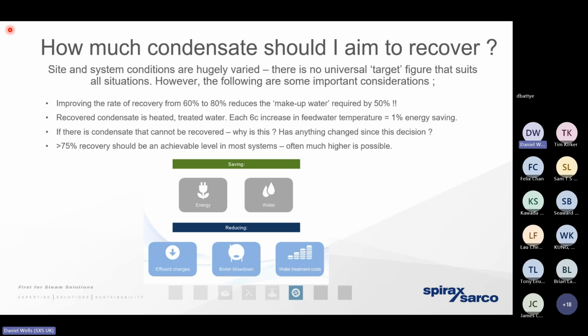It's a little bit more tricky than that, because we know that our client is highly likely to have a number of steam traps that maybe failed in the open position. We know that we may need to vent condensate away if it becomes depressurized and expands significantly. We know that we may have the occasional leaking steam valve or pinhole in pipework, for example. So it's fair to say that in the vast majority of applications and cases, we can work on a rule of thumb that says we should really be looking to recover about 85% of all of the steam that is being generated in the form of recovered condensate. So if we're generating 10,000 kilograms of steam per hour, we'd like to think that we're in a position to recover about 8,500 kilograms of condensate.